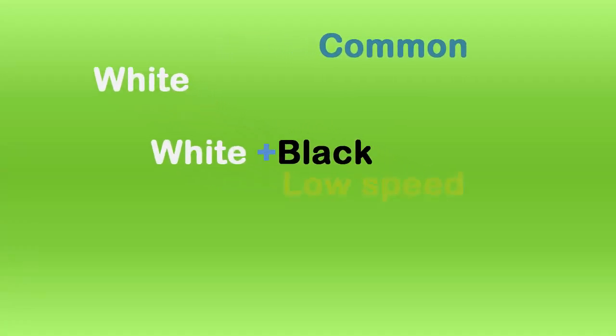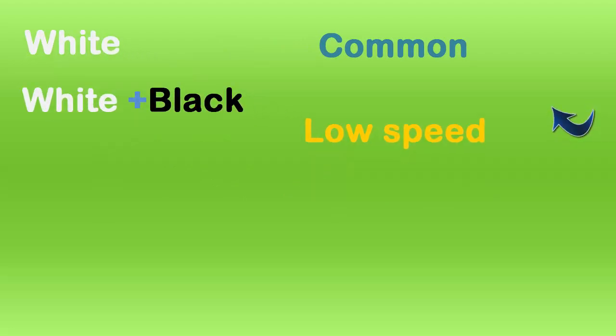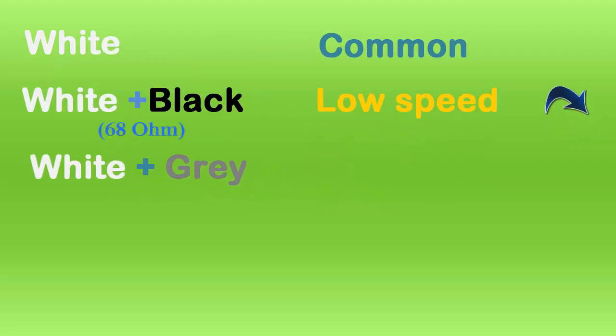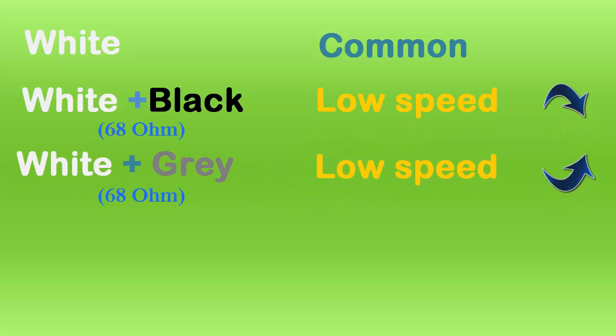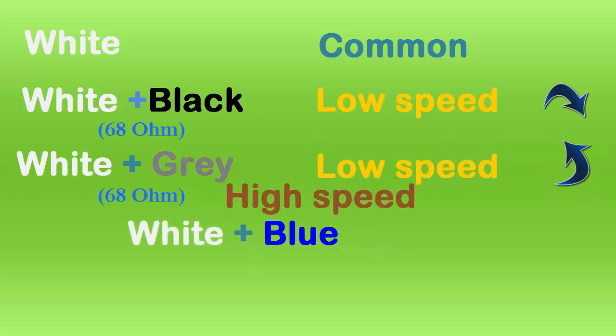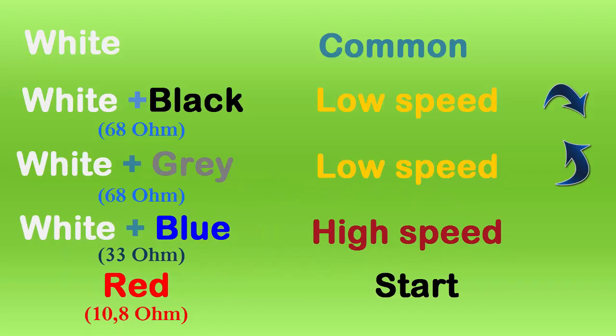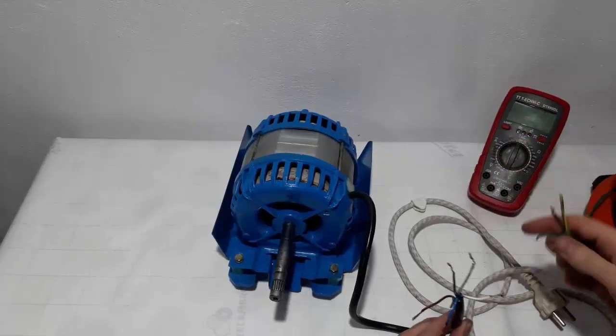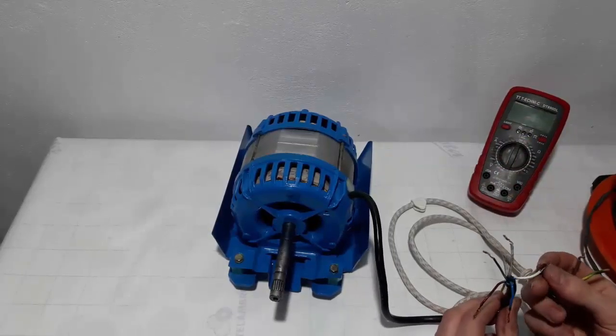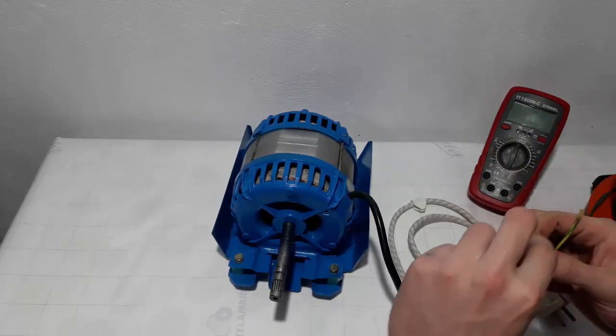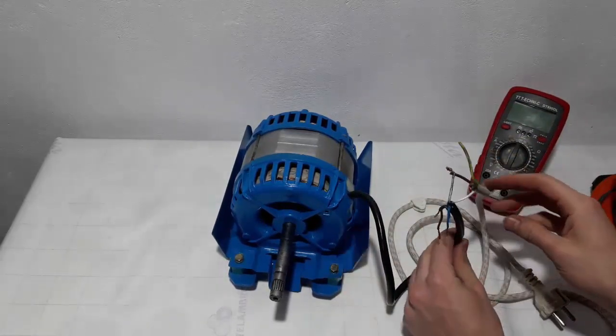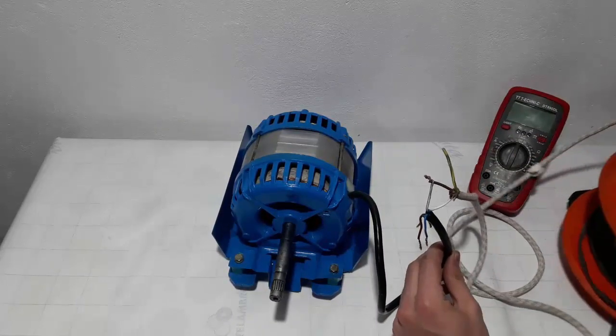So the white is the common. White and black for the low speed. White and gray for the low speed but for the opposite direction. White and blue for the high speed, and the red one is for start. Now we will connect the engine according to the colors which is determined. Connecting the white and gray one for the low speed.